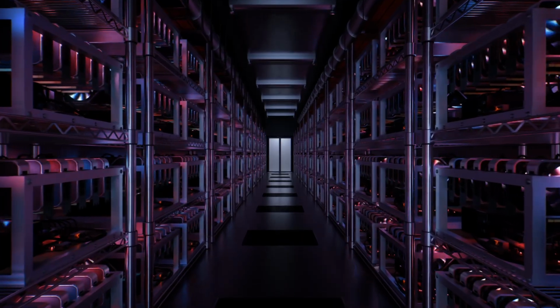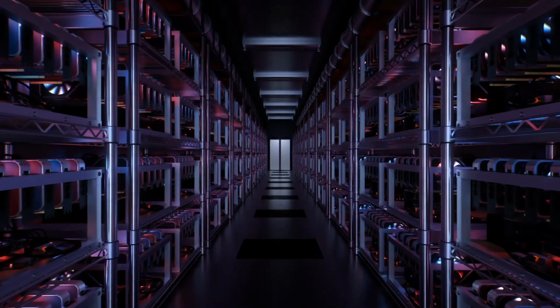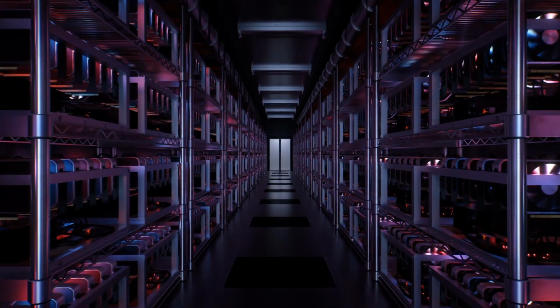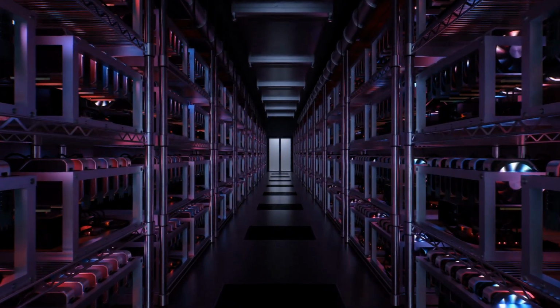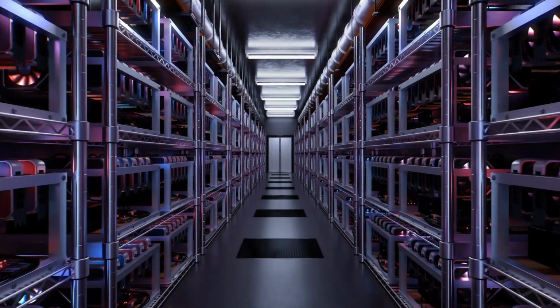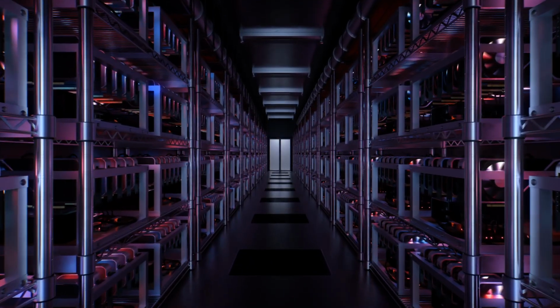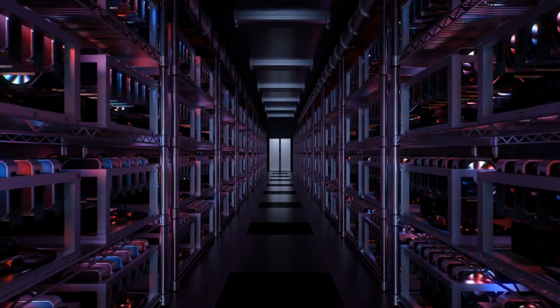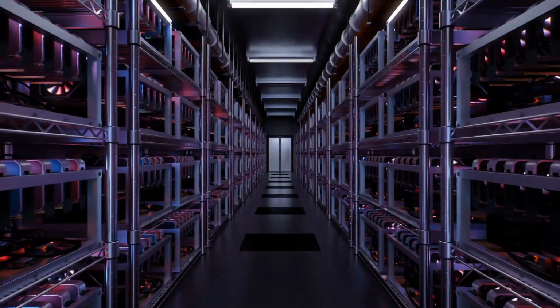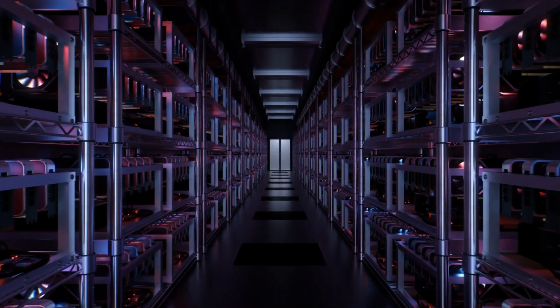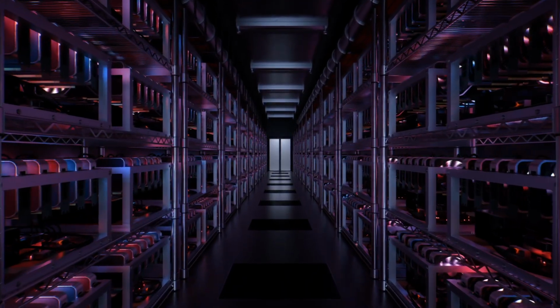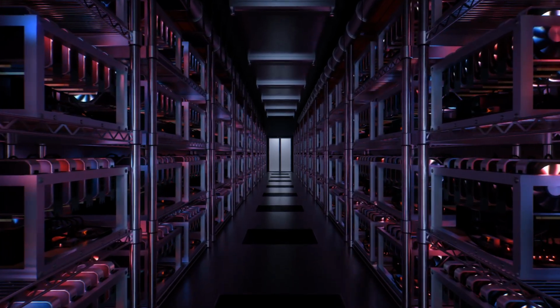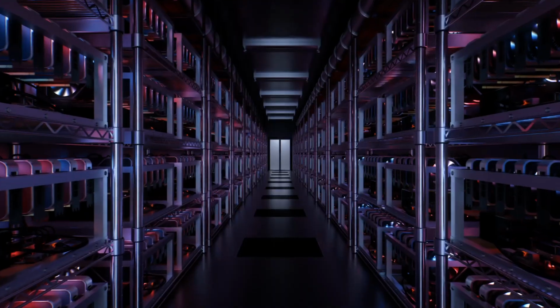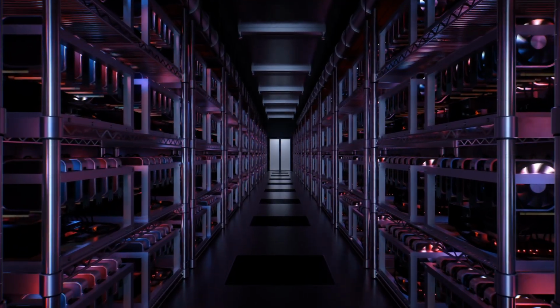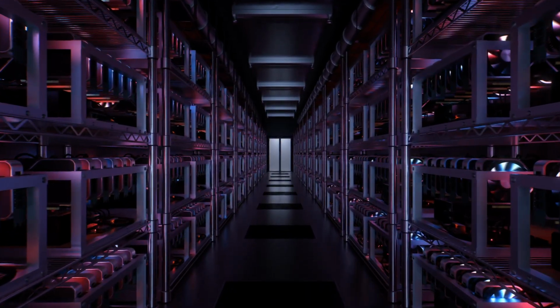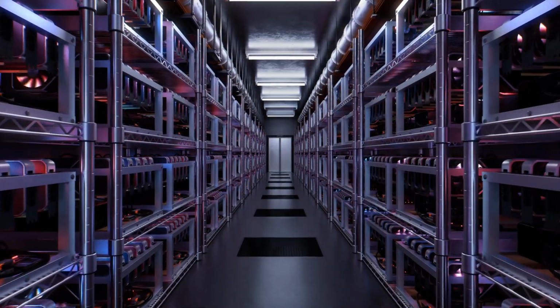But pumping pure water through the microscopic cooling channels inside millions of dollars of computing equipment introduces three catastrophic liabilities. First, freezing points. The primary facility water can enter the building at 2 degrees Celsius, barely above freezing. If your secondary loop runs pure water and the AI servers suddenly drop their workload, meaning they stop generating heat, that 2-degree facility water can cause localized freezing inside the heat exchanger, and ice expands. Expanding ice inside a high-pressure titanium manifold will rupture it instantly.